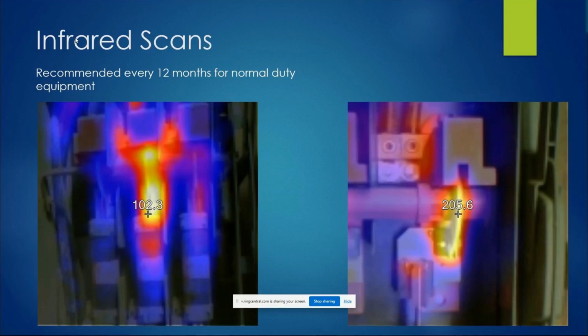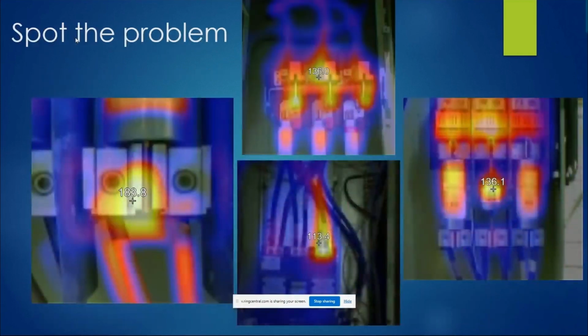Looking at these two particular scans, you can already identify what's happening in some of these features. You can see that in the middle load, the high heat signature comes from resistance and from a poor connection. It could be an overload condition, but each one of these looks like it's just that: it's corroded and there's a bad connection at that location. And as the heat signature increases, the corrosion increases. It's a catastrophic event just building. It doesn't improve over time. It just gets worse as the heat builds up, more corrosion, more resistance, and then more heat.